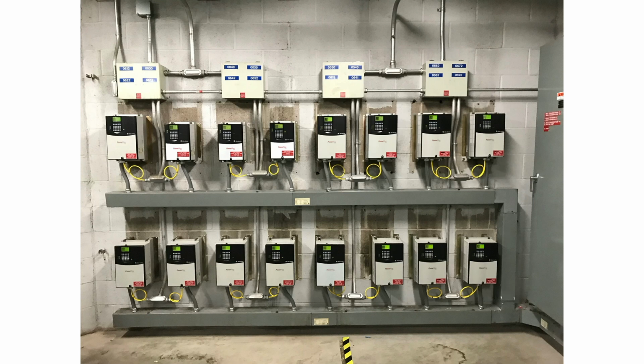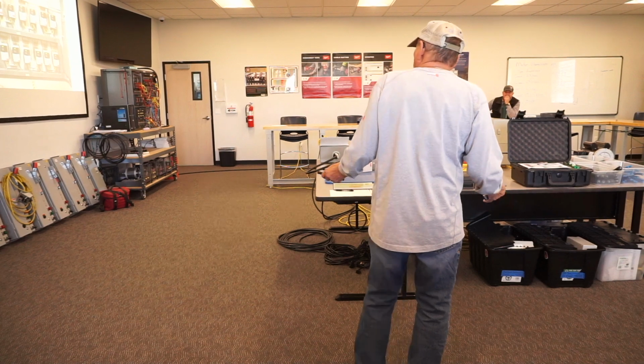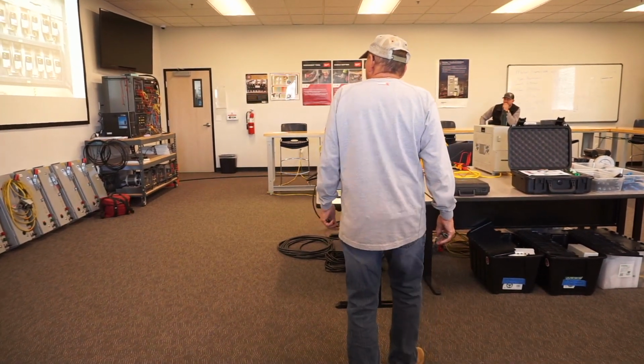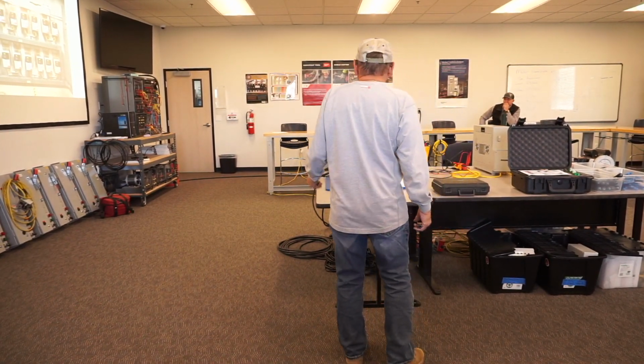So, this was a job I was called out on. They were losing drives, motors. Anybody recognize a problem with this installation? As you can probably see from the dark spots here, these old drives got replaced with new drives. This room had 52 drives inside this room. This room, not a main electric room, but an electric room. And the drives were installed in this electric room.